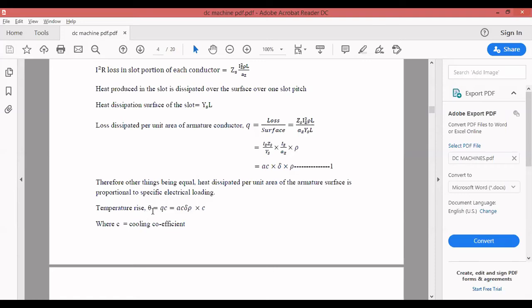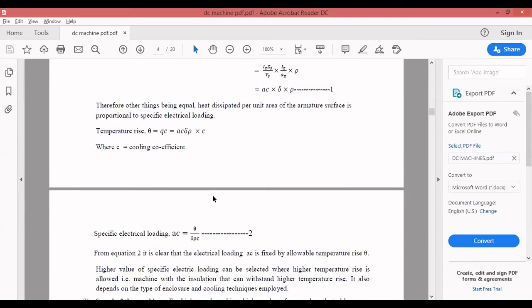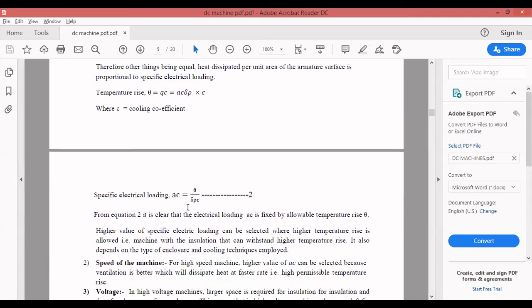Next, size of the machine: in a large size machine, more space is available for accommodation of conductors in a slot, which permits selection of a higher A_C. Next factor is armature reaction. When a high value of A_C is selected, a higher value of armature MMF makes the armature magnetically very strong. Under loaded conditions, large air gap flux distortion weakens the main flux.